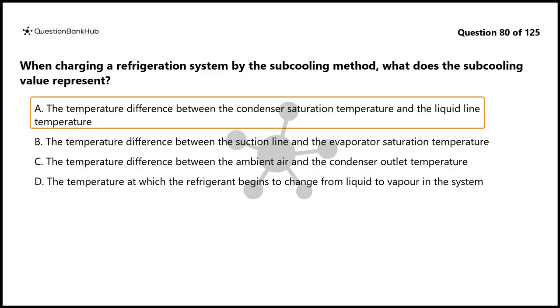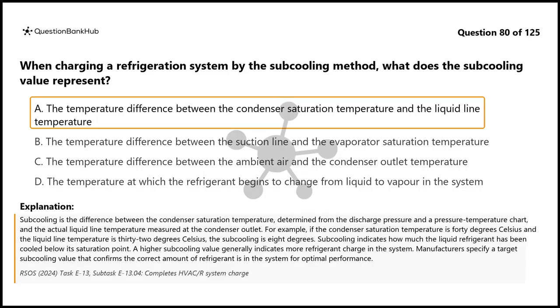The correct answer is A. Subcooling is the difference between the condenser saturation temperature, determined from the discharge pressure and a pressure temperature chart, and the actual liquid line temperature measured at the condenser outlet. For example, if the condenser saturation temperature is 40 degrees Celsius and the liquid line temperature is 32 degrees Celsius, the subcooling is 8 degrees.